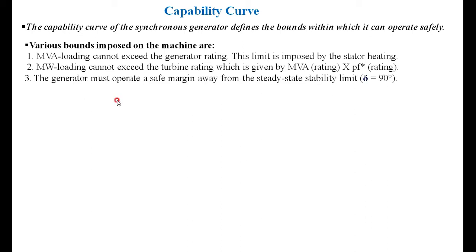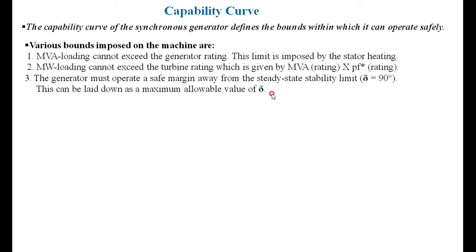The third limitation is that the generator must operate at a safe margin away from the steady state stability limit. This means you should not exceed the load angle beyond 90 degrees, within which you have to operate the generator. Whenever there is loading, there is an increase in the load angle. You should not exceed the load angle beyond delta equal to 90 degrees, within which the generator will operate safely. The maximum allowable value of delta is less than 90 degrees.